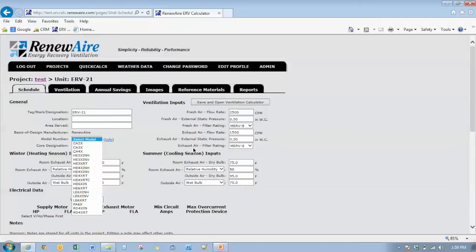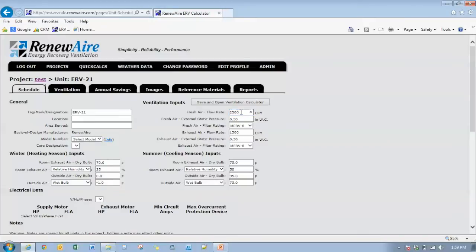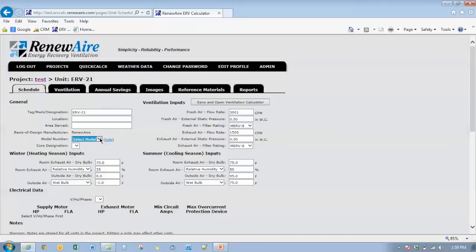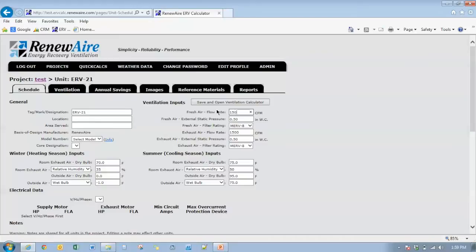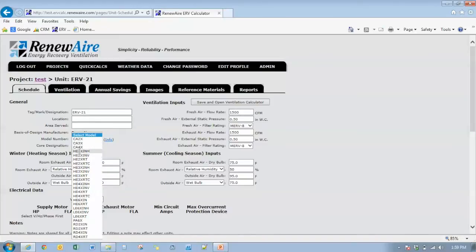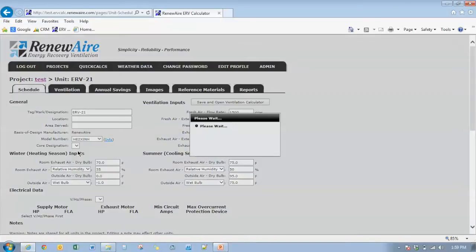We also have a limitation so that you can't unbalance the airstreams by more than 50%. So if we change one of these airstreams to 3001 CFM and go back to the models, you see I get no option of selecting a unit to achieve that level of unbalance. So we're going to go back here to 1500 CFM.